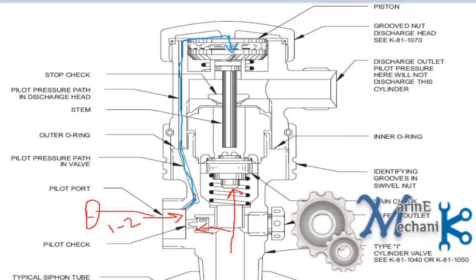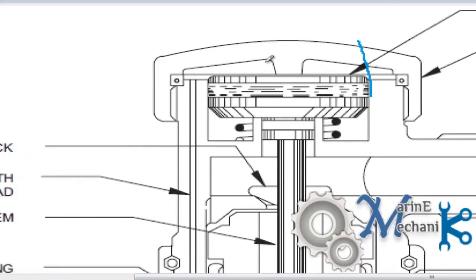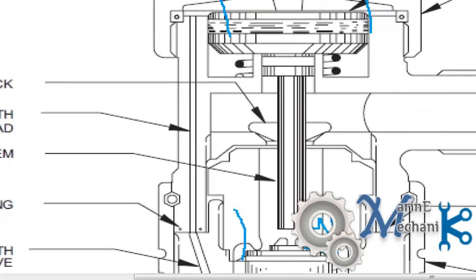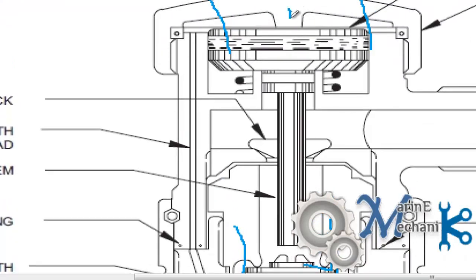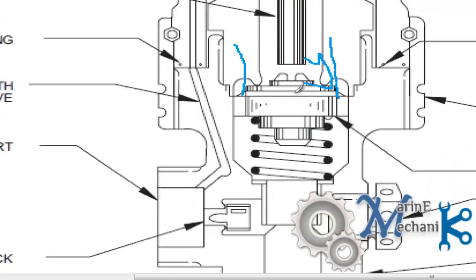The piston moves down. You will wonder how the lesser pressure CO2 can open this valve against the higher pressure CO2 inside the bottle. It's very simple. The idea is having a large area piston. I'll explain once again. I'll enlarge the picture. Now, when you see the area of this piston, let's say this is X. This piston area is more when compared with this. So, as the area is more, with the hydraulic basics, a smaller pressure is sufficient to push it down. And as it is pushed down, the stem moves down and then opens this valve.